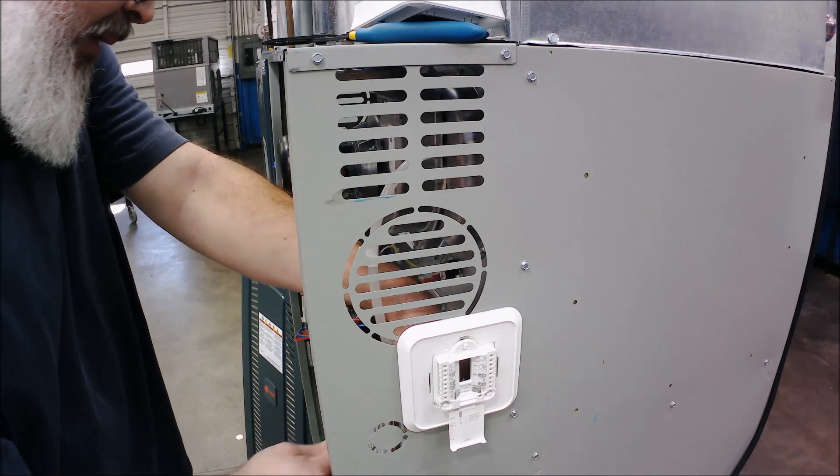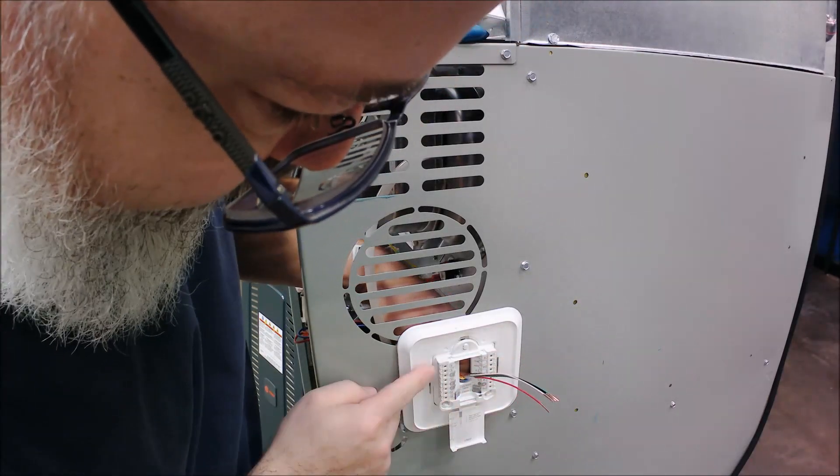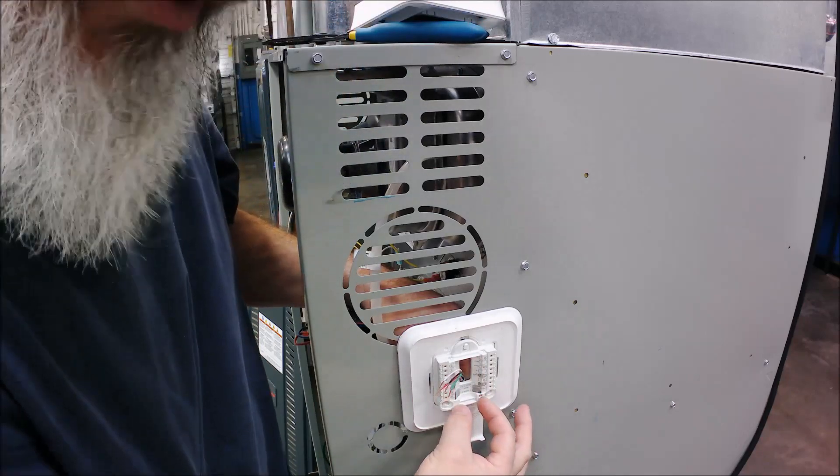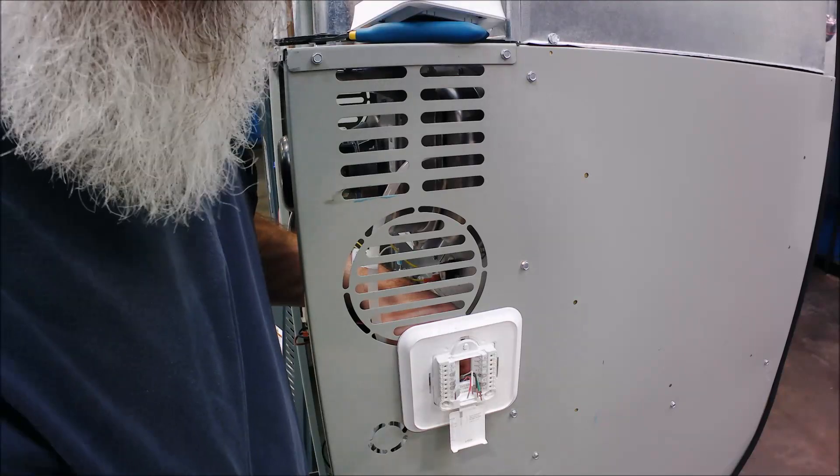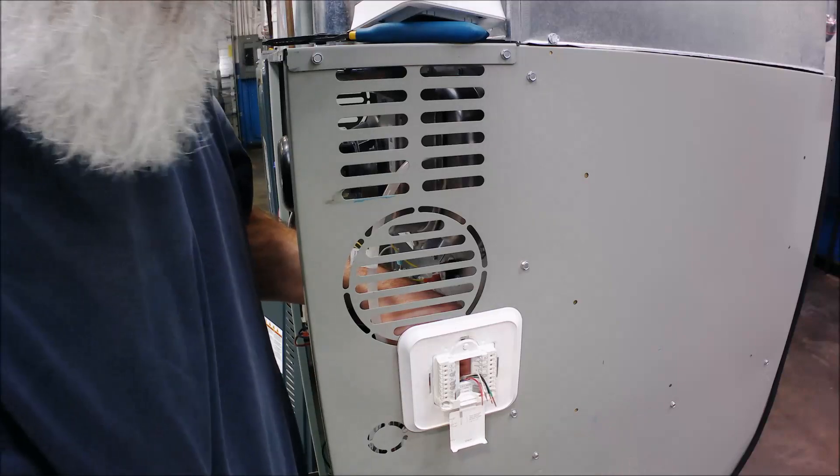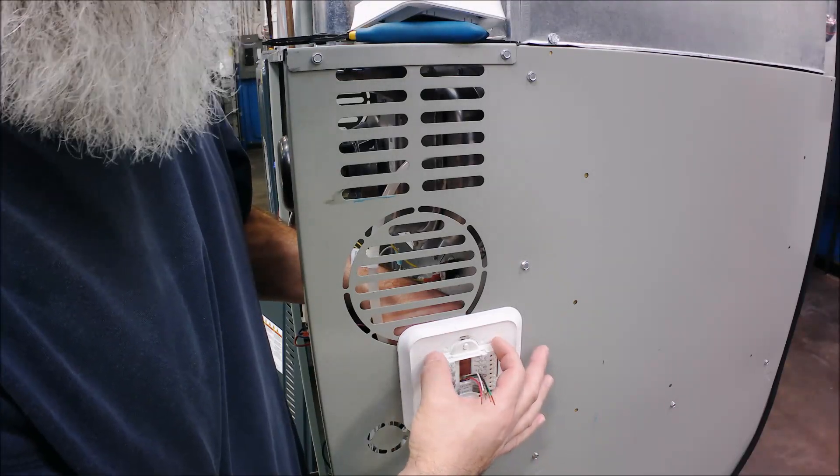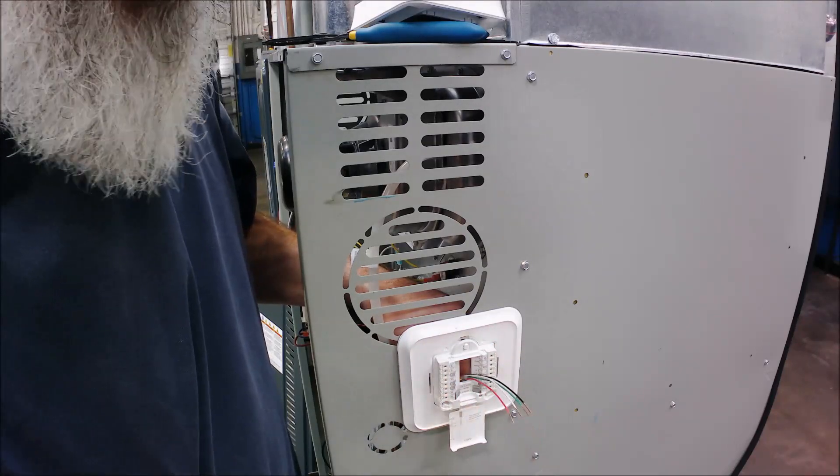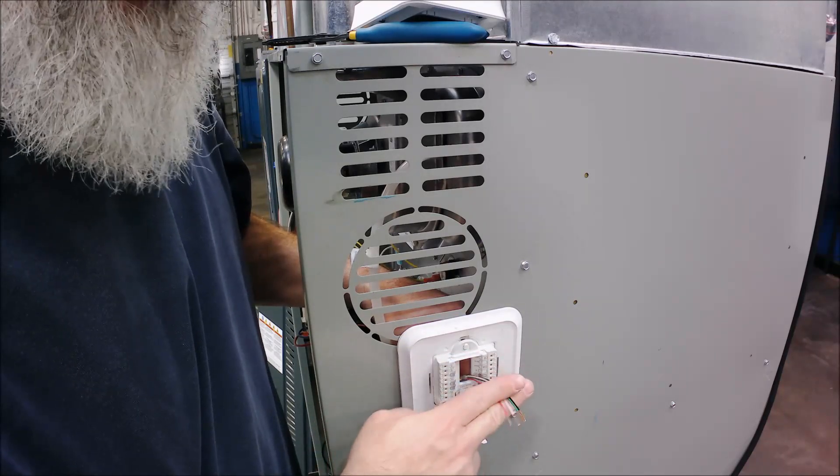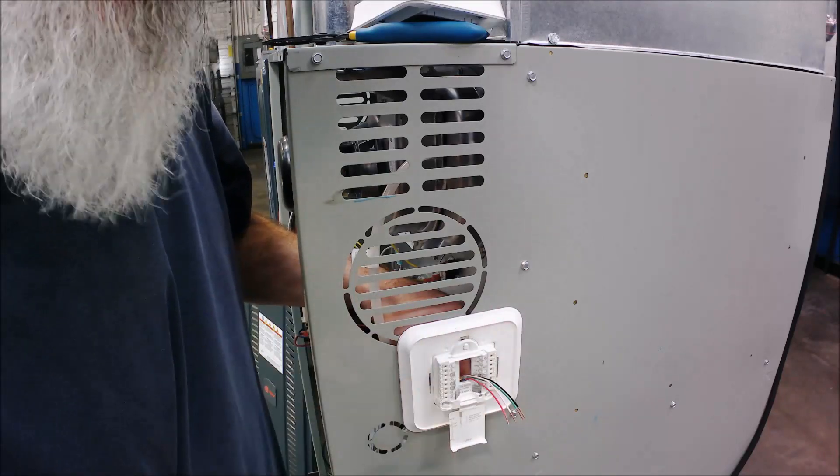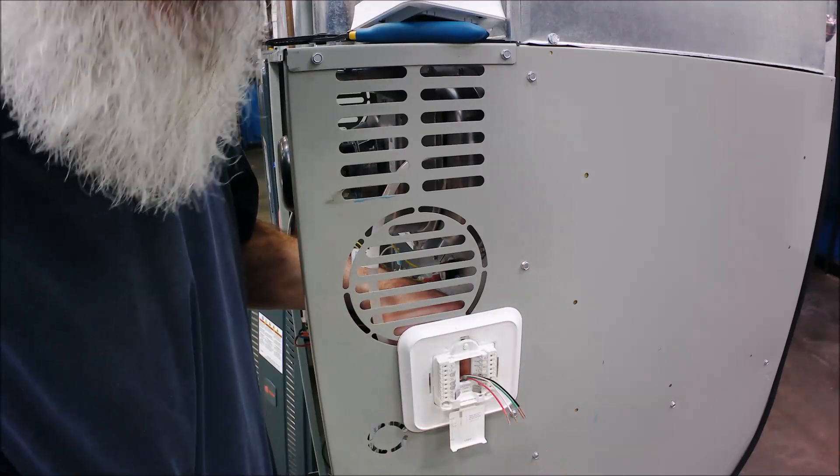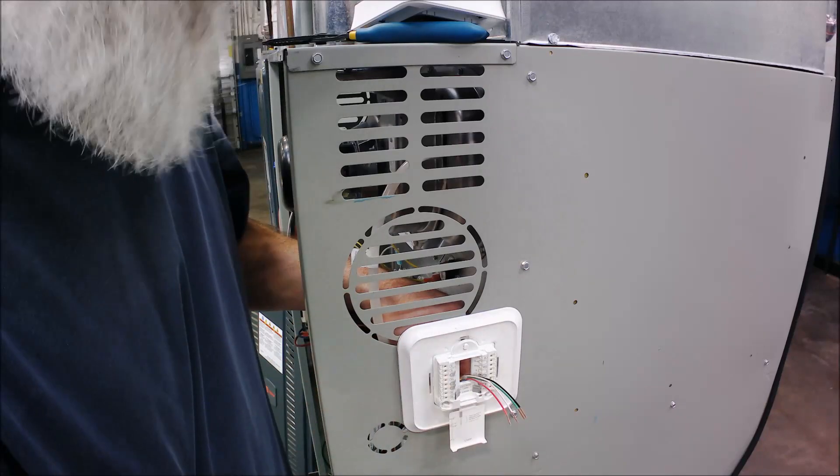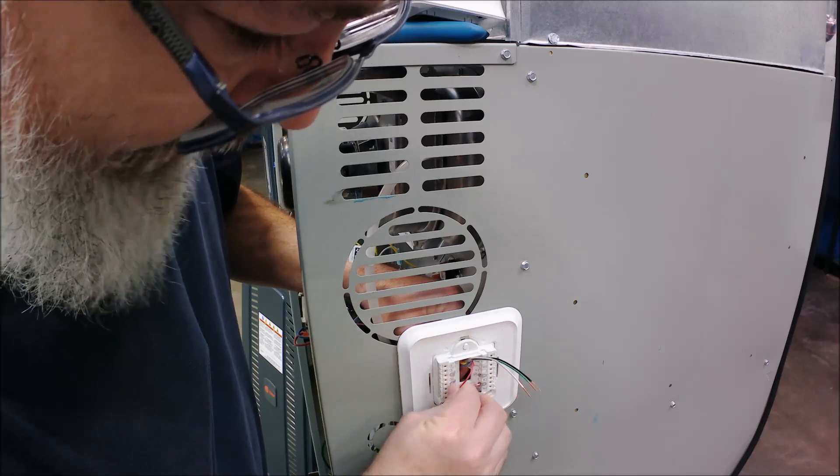Usually when you buy these digital thermostats, they're capable of doing multiple types of units—heat pumps, heat-cool systems, heat-only, cool-only. You have to read the literature and program it correctly. Just because I know I have a heat-only unit and the circuits I'm using doesn't mean the thermostat knows that. I have to go into programming and tell it what it is so it does the right sequence of operations.